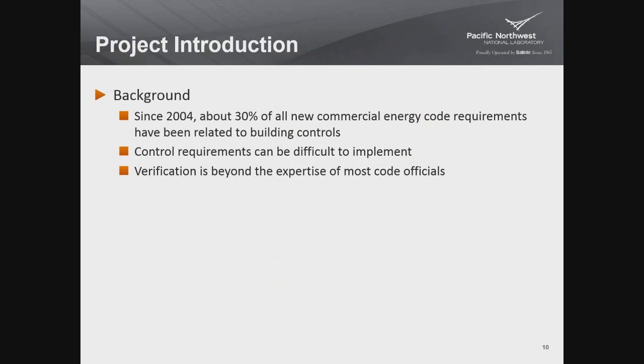A little more background. David mentioned we did a little survey of all the changes to the commercial energy code since 2004, and about 30% of those were related to building controls, so about a third of them had something to do with building controls. Control requirements are difficult to implement. Verification is really beyond the expertise of most code officials. They're not trained mechanical engineers for the most part. Maybe in some large jurisdictions they are, and it's very complicated to verify controls.